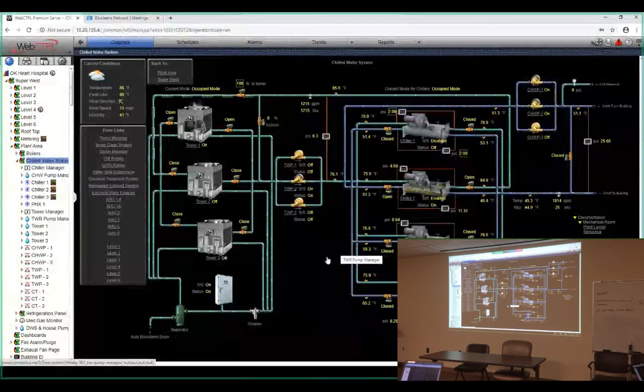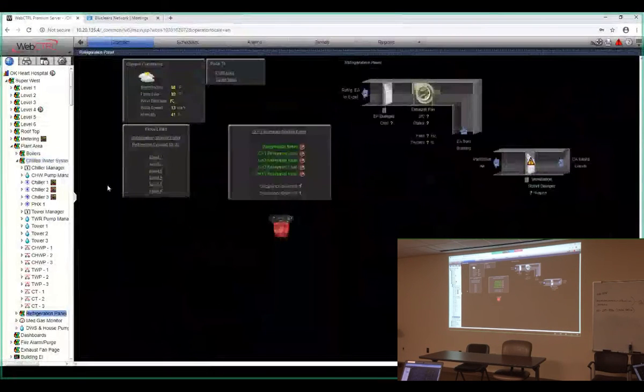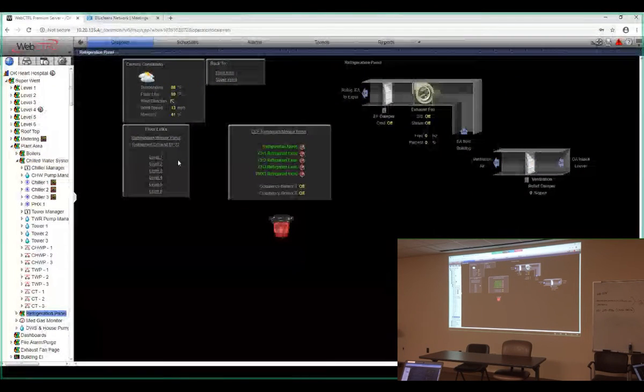Let's go to, looks like that next one. Chemical treatment. Let's go to refrigerant exhaust. Okay, refrigerant alarms and exhaust systems. Under the refrigerant alarm, we're going to start that exhaust fan and open the ventilation into the space. We've got a refrigerant alarm. We've got a chiller 1, chiller 2, and chiller 3 refrigerant leak.